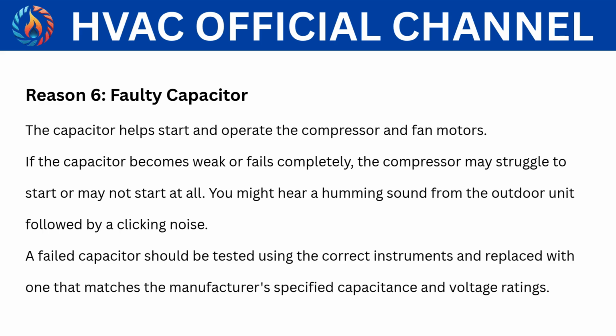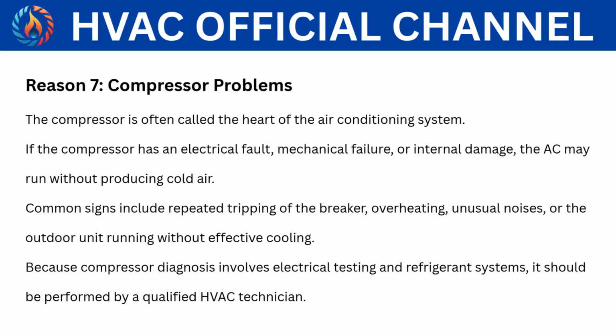Reason 6. Faulty capacitor. The capacitor helps start and operate the compressor and fan motors. If the capacitor becomes weak or fails completely, the compressor may struggle to start or may not start at all. You might hear a humming sound from the outdoor unit, followed by a clicking noise. A failed capacitor should be tested using the correct instruments and replaced with one that matches the manufacturer's specified capacitance and voltage ratings.